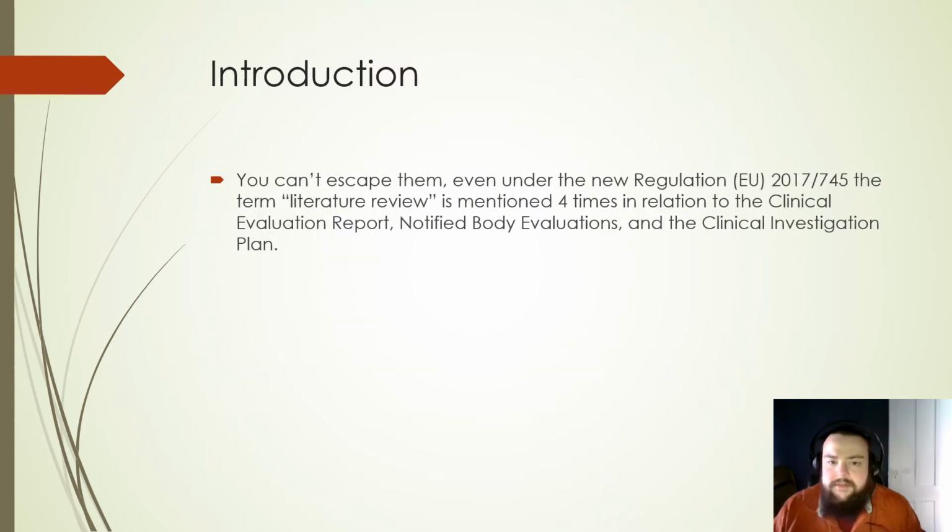So not only can it be a large task, it is a task that you have to do. And it's not something you can escape from in the new regulation EU 2017/745. The term literature review is specifically mentioned 4 times, and it's mentioned in relation to the clinical evaluation report, notified body evaluations, and your clinical investigation plan.